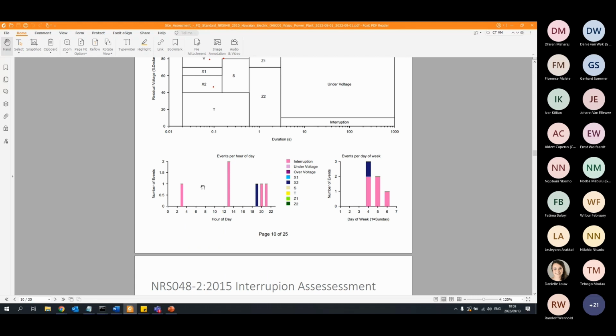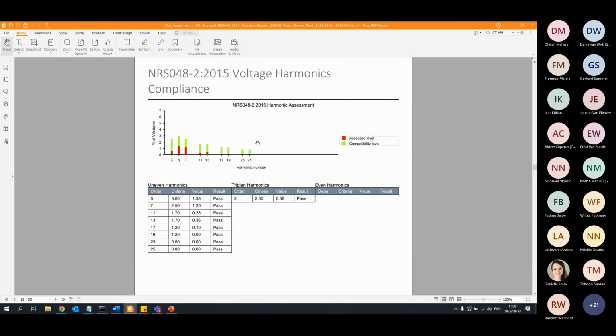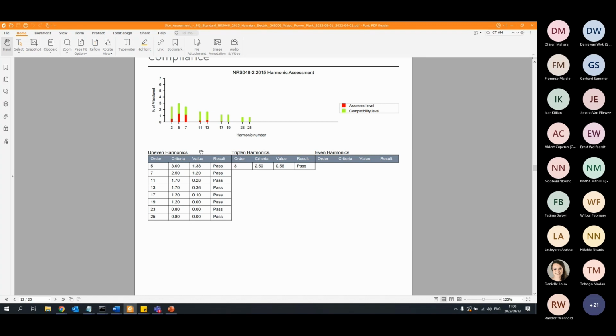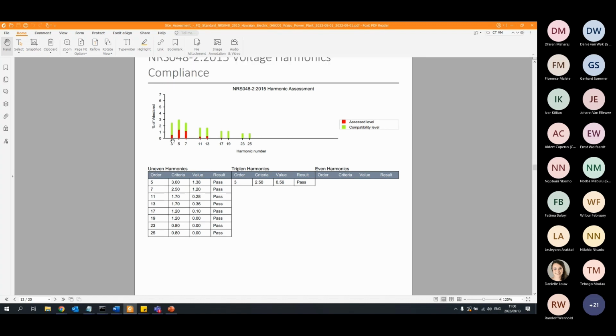It shows you when in time, and there are statistical graphs that show you what hours of the day the events happen, to see if there is any specific pattern, and then in terms of what day of the week. So over a long period of time, this data becomes very valuable to assess if there are specific trends that you recognize, maybe seasonal trends or hourly trends, and so on. And then lastly, it's the voltage harmonics that are compared to your limits. This is for an HV network, and we see the individual voltage harmonics are all compliant and also below the compatibility level.